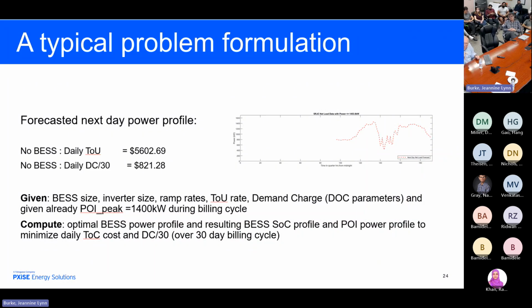This is showing the next day profile. This is how much it costs if you do nothing. You are given the battery size, the inverter size. You're given ramp rates on the battery. You're given a time of use. You're given a demand charge. You're also given your worst POI peak for the last billing cycle. And then you compute the power profile over the next 24 hours for both the SOC of the battery and the POI, the point of interconnection.